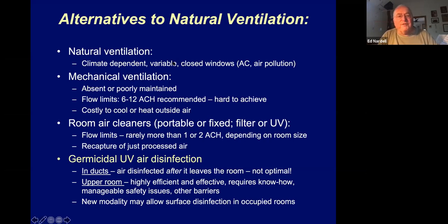Natural ventilation is fine if you can open the windows and if the conditions are right outside. Mechanical ventilation, in poor countries, is often absent or poorly maintained, and sometimes in rich countries too, it's poorly maintained. And it's limited. It's hard to get up to the 6 to 12 air changes that CDC recommends, and it's costly to cool or heat outside air.